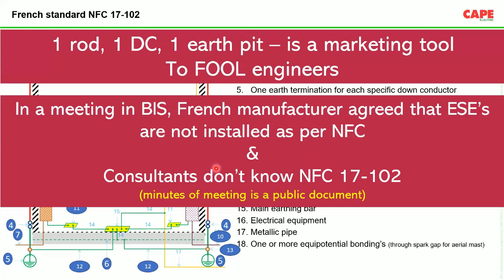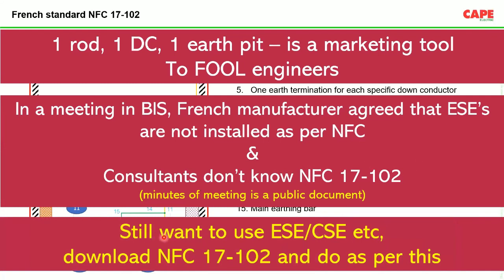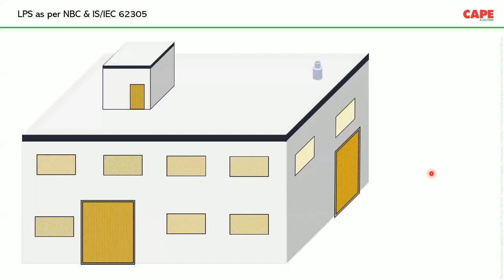And they also blamed that the consultants don't know about the French code. As a result, the consultants are responsible for the one rod, one down conductor, one earth electrode. Consultants or the safety auditors are responsible, and the manufacturer is not responsible. Basically, they made the story of one rod, one down conductor, and one earthing, sold it, and finally they say, I'm not responsible. If you still want to use these non-standard items, please download the National French Code NF C 17-102, then do as per this particular code. Don't believe the manufacturer's claim of one rod, one down conductor, and one earth pit, because it is just to fool engineers and to make business.